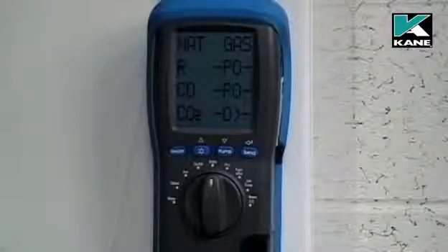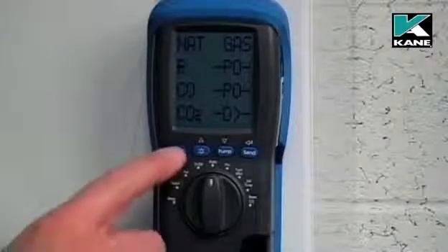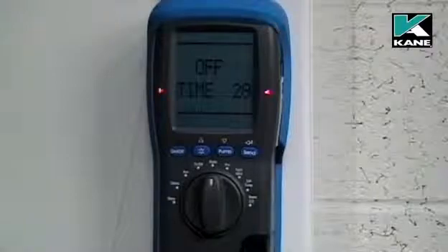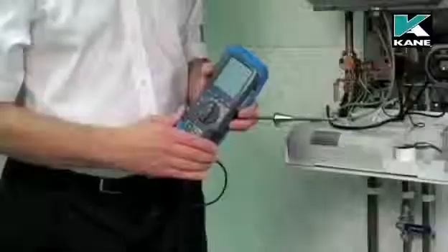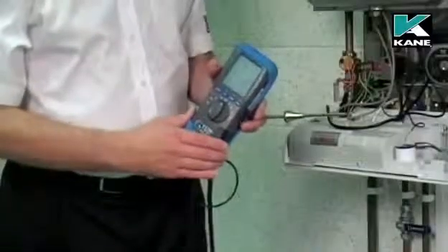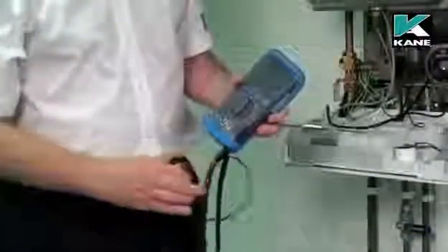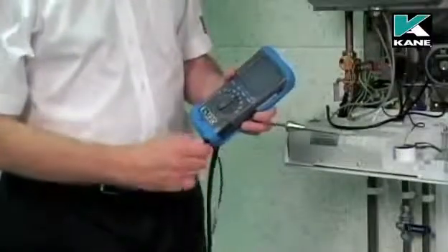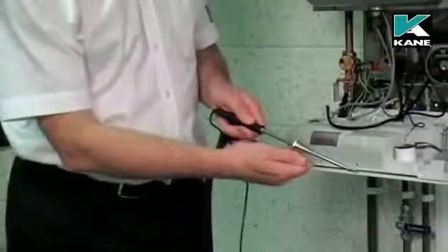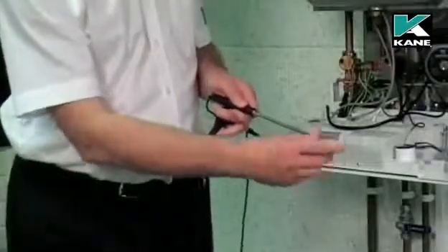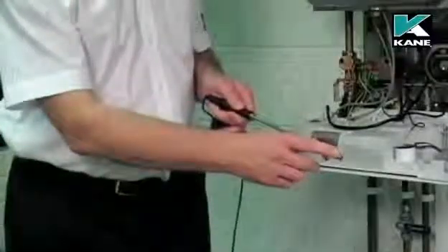When you've finished your combustion tests, switch the instrument off and it will automatically go through a 30-second purge cycle to make sure there's fresh air in the analyzer. When you finish your combustion test, disconnect the thermocouple and the flue probe hose, wait for the probe to cool, and then move the adjustment cone over the tip of the probe to protect the thermocouple.